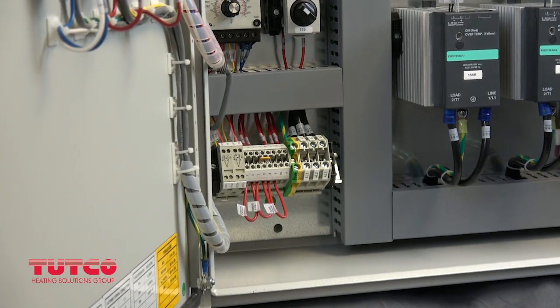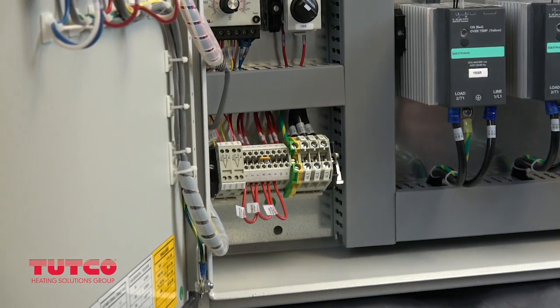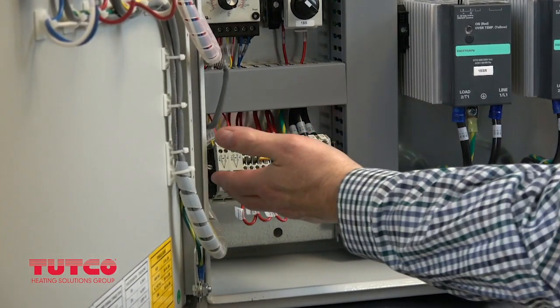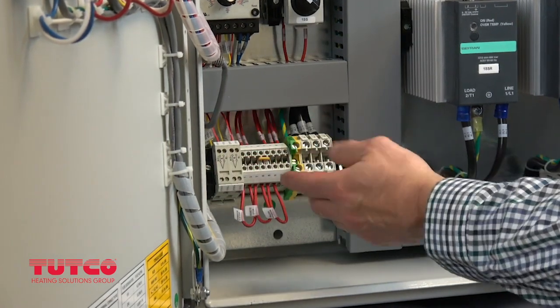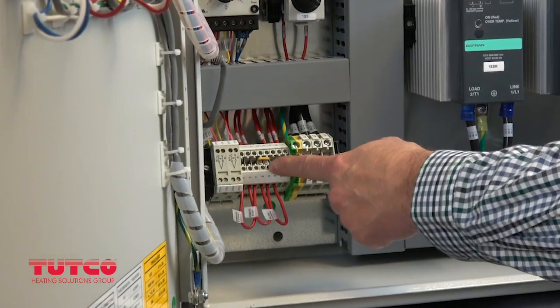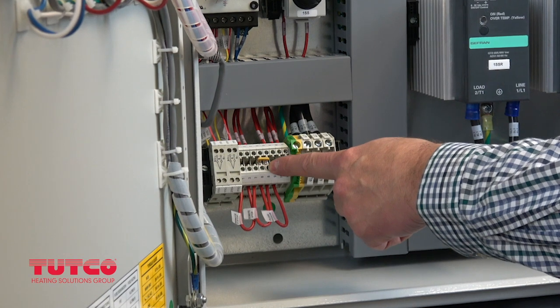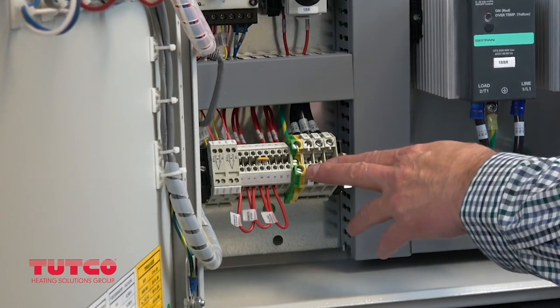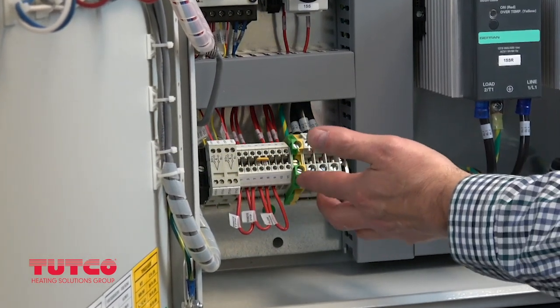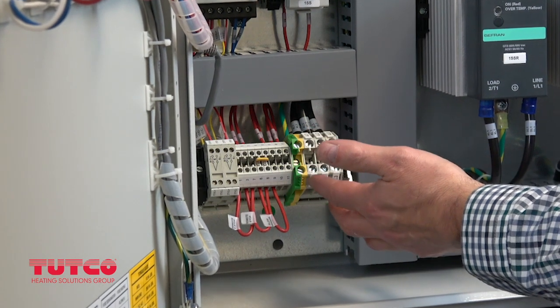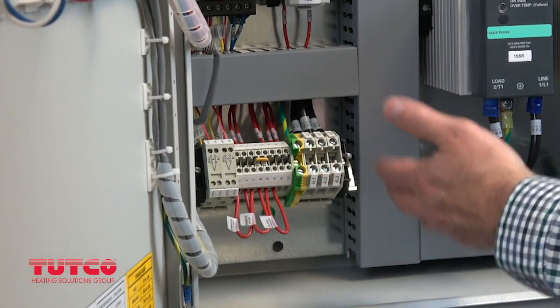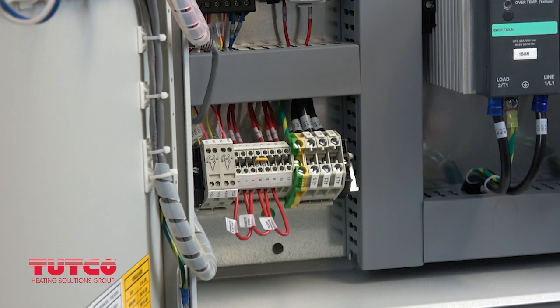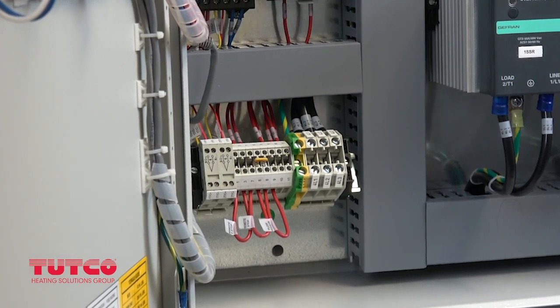With the input power configured properly, move on to the heater connections. In the bottom left-hand corner of the control panel are the heater wiring connections. Thermocouples, start, stop, and remote e-stop connections are all angled in the DIN rail for easier termination. The heater ground terminal and the L1, L2, and L3 terminals are used to connect the heater.